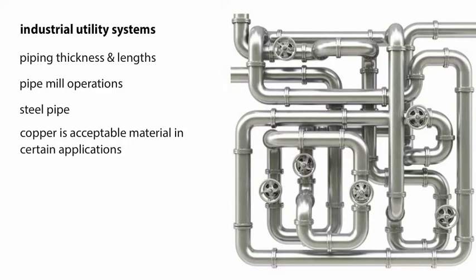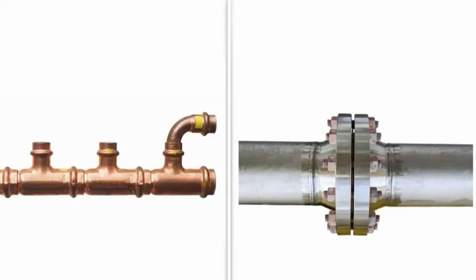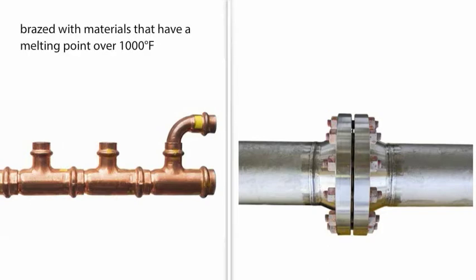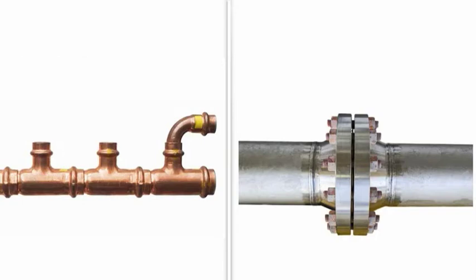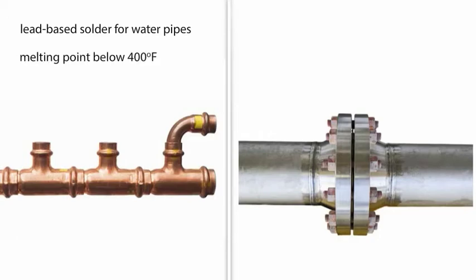If copper is used, the joints must be brazed with materials that have a melting point of over 1,000 degrees Fahrenheit. Most commonly used brazes, but not solders, meet this requirement. This is different from the typical lead-based solder used for water pipes, which has a melting point below 400 degrees Fahrenheit.